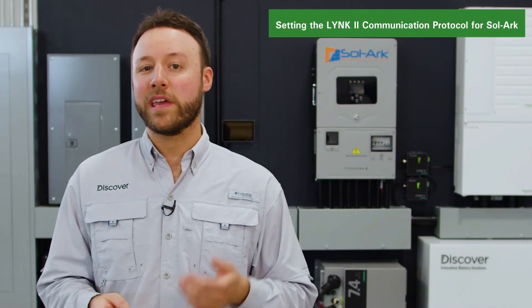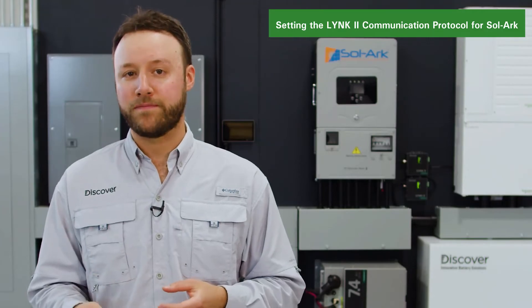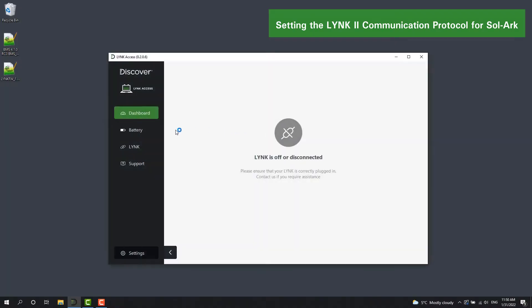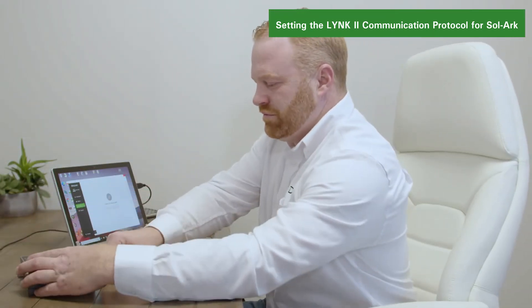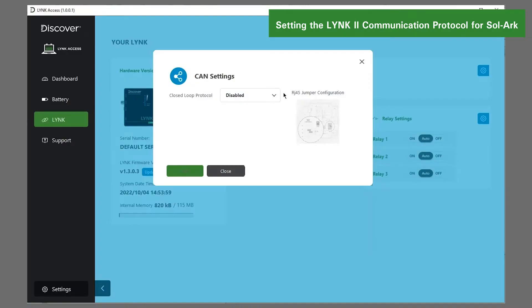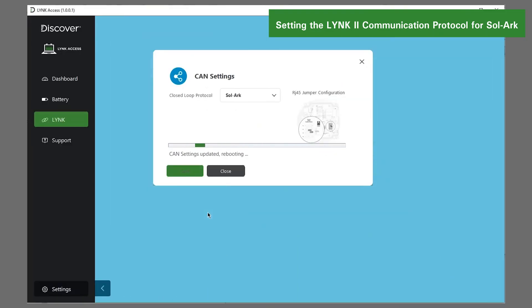After establishing the open-loop configuration, we can configure the LYNK II gateway to use the Sol-Ark communication protocol. To begin, download and install the LYNK Access software to a Windows-based PC from the Discover Battery website. Then open LYNK Access, connect your PC to the LYNK II gateway using the USB Type-B mini plug cable that comes with the LYNK gateway. Select the Sol-Ark communication protocol using the LYNK Access software and save the setup.